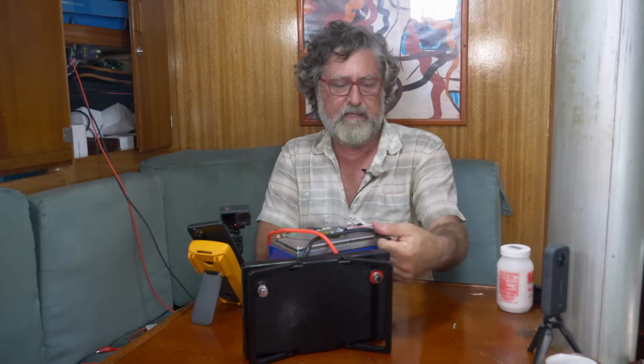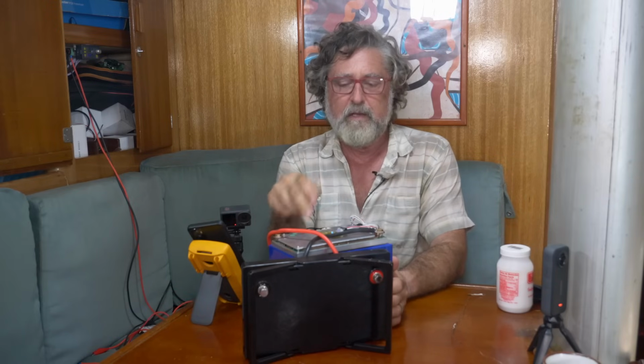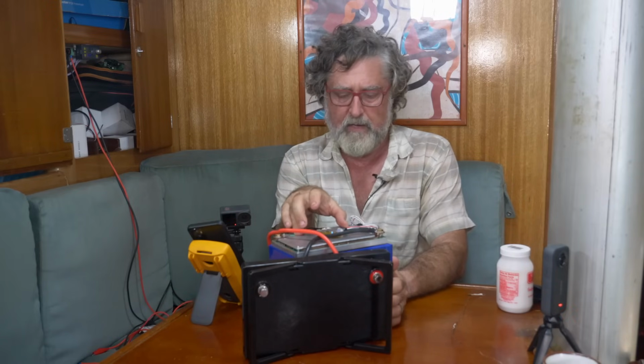Okay, so the next thing we're going to do, this battery is now fully charged. We're going to take this back to what I call the sauna room, the tool room, hook it directly to my inverter, and using a heat gun, we're going to pull some real power out of it. It's rated for 100 amps, so we're going to pull 100 amps for a period of time. We're going to take a look at it with an infrared camera and see if it's getting hot anywhere.